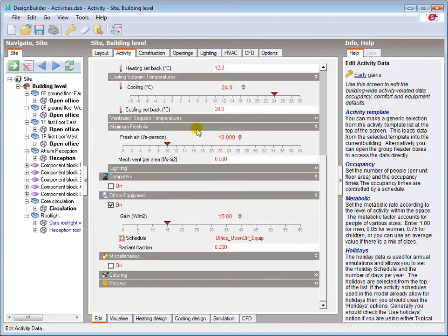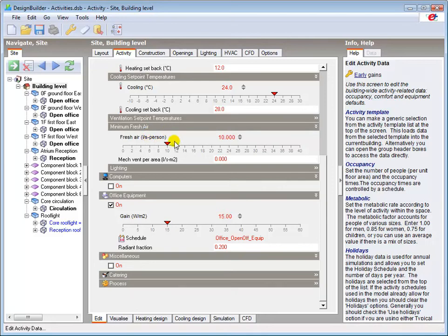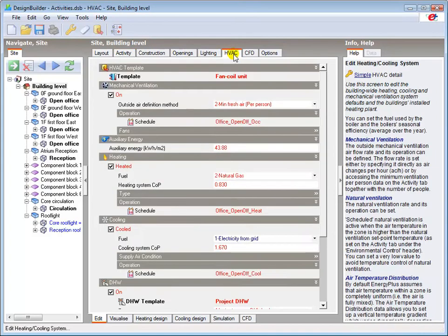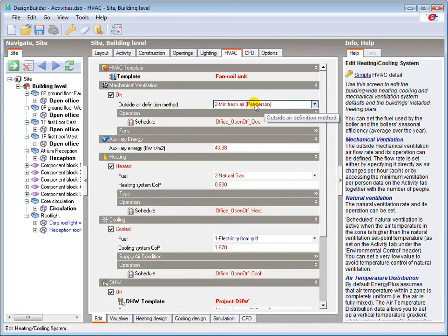The minimum fresh air set points govern the air flow rate to the zone when mechanical ventilation to the zone is enabled. The airflow rate can be based on either occupancy or floor area, or both, depending on the outside air definition method selected in the mechanical ventilation header of the HVAC tab.